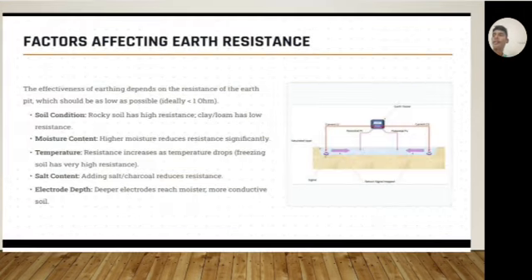Last and final one, factors affecting earth resistance. The resistance of earthing depends on the resistance of the earth pit, which should be as low as possible. First one, soil condition. Rocky soil has high resistance. Clay loam has low resistance. Second point, moisture content. High moisture reduces resistance significantly.